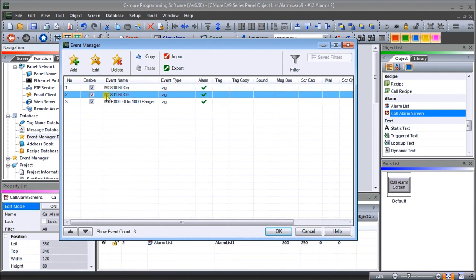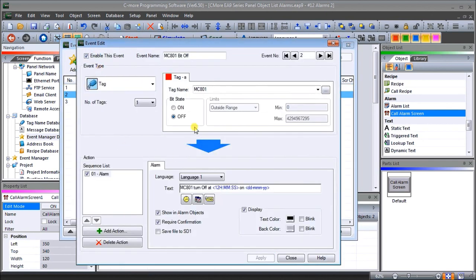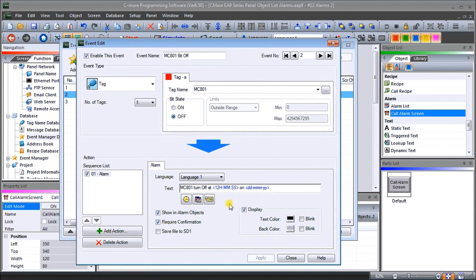Looking at our second alarm — let's edit it. We have MC801 and we're calling the event name 'MC801 bit off'. After setting the tag, we go to language one again — the text is going to be 'MC801 turned off at', then the date and time. In this case we're going to show the alarm objects as before, and we're going to require confirmation — meaning when the alarm comes off it will still be displayed until someone confirms it as a valid alarm. We'll also turn on our display so we can see that alarm on any page we have programmed.